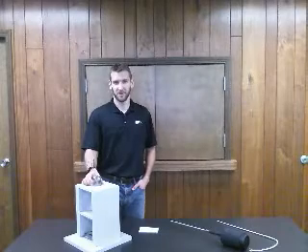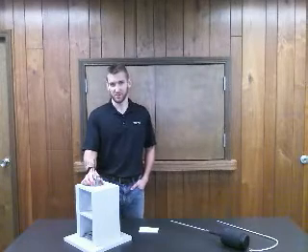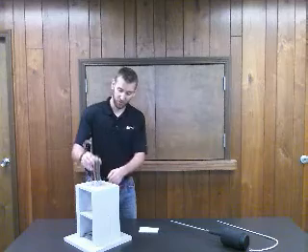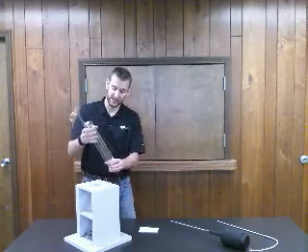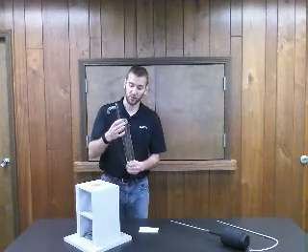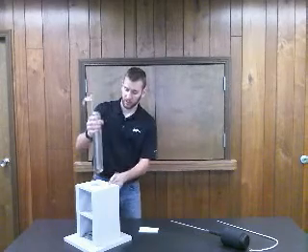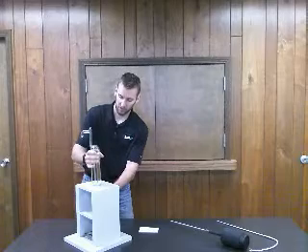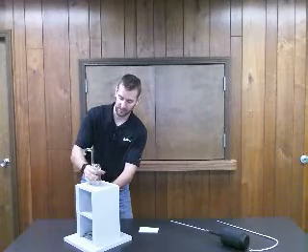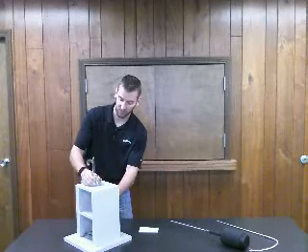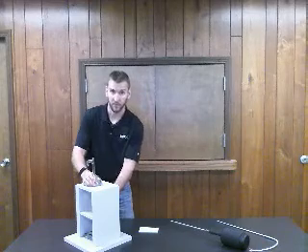Hello. Today we will be going over the triple point water cell. The triple point water cell is a sealed glass container that has a glass well that goes down its center. The water in this cell can exist in solid, liquid, and gaseous forms all at the same time.